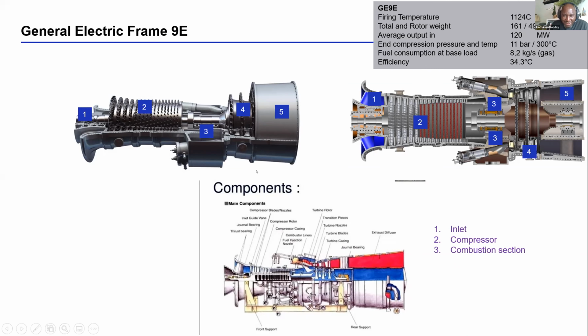So, in the cans, you have the burner, which is called the fuel nozzle, where the ignition happens, where the gas comes in. Then you have the combustion liners, which stream the hot flame. Then it goes through a transition piece, which kind of narrows the movement of the hot air into the turbines, which now extracts that heat energy, and under rotation converts it to mechanical energy. So the GE gas turbine, the frame 9E, has 3 bearings. So these are standing on 3 bearings. This is bearing number 1, bearing number 2, and bearing number 3. So it's a 17-stage compressor. It has a 17-stage, 3 bearings, 14 combustion cans, 3 turbine stages.